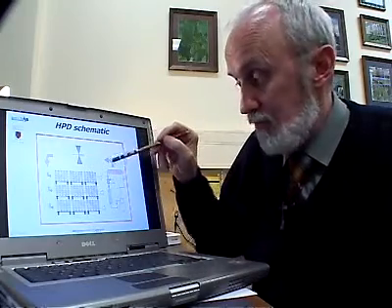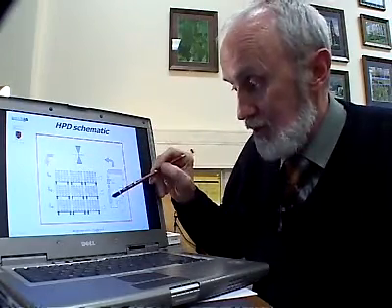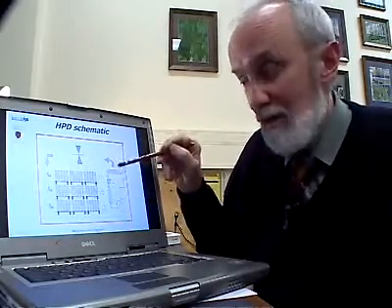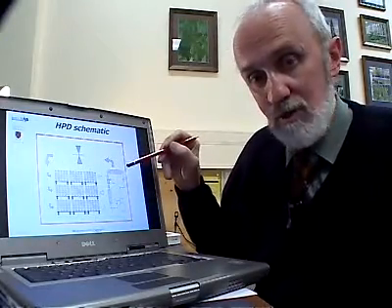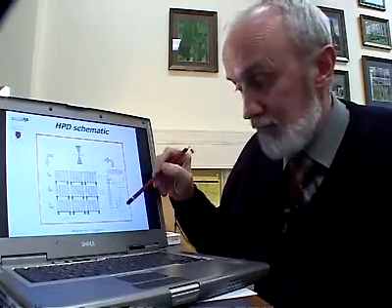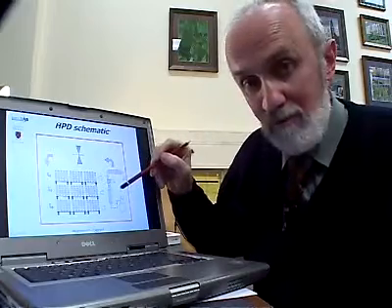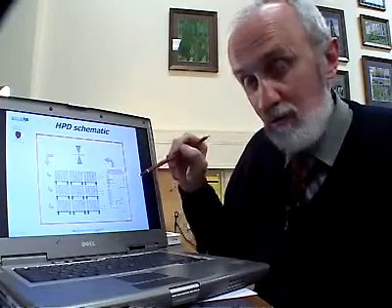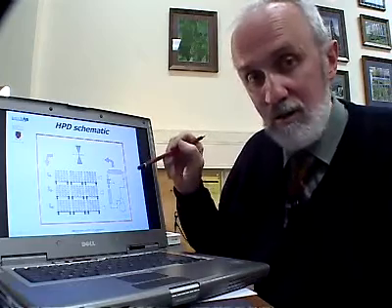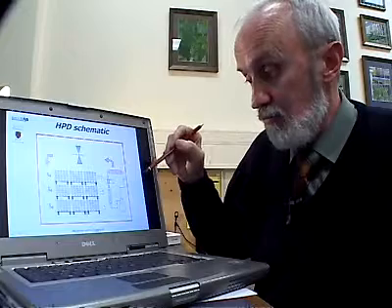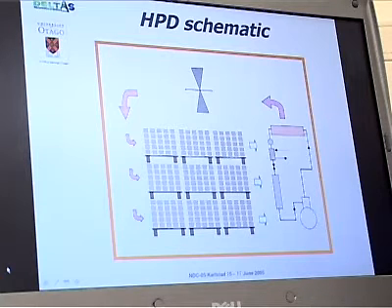So there's all these trade-offs between the area here, the area there, airflow through this, airflow through that, the airflow through the stack, where you try to balance out all these different things so that you actually produce something which has the minimum power consumption, at the same time at the minimum overall cost, and at the same time has the maximum amount of moisture flow. And that can only be done by detailed computer modeling, which is something that we've worked into a position where we've got enough experience that we're quite confident about our computer models.